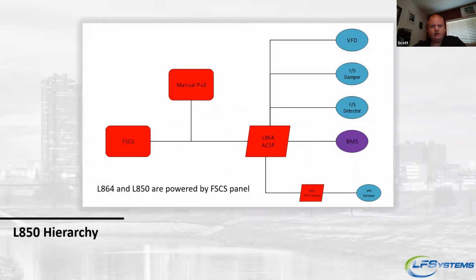Let's take a look at the hierarchy of the 864 and the 850s. So again, as you see, the FSCS or manual pull activates the 864. The 864 sends a start-stop signal to the 850, and the 850 controls the IPR damper independently. Now, the 864 then again controls your VFD, fire smoke damper, and fire smoke detector, and feeds information to the building management system if needed.